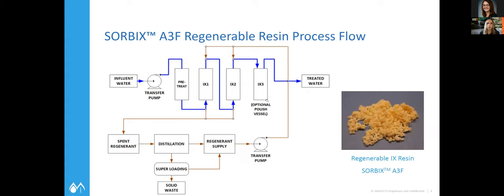Here's a process flow of what the system looks like — we have a picture as well. It's very similar to a water softener process. We have a regenerant solution, which is an alcohol and brine solution, to regenerate that media and collect the PFAS off the media so that you can reuse it. A big question is whether you're retaining the capacity of the media, and what we've seen so far is that we're able to maintain the resin's capacity to hold on to PFAS.